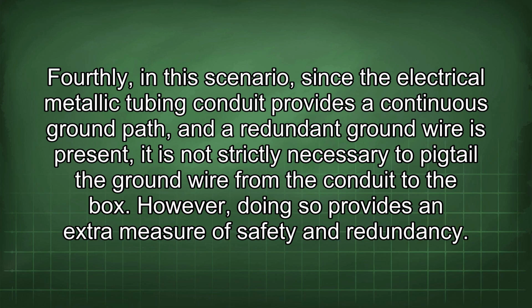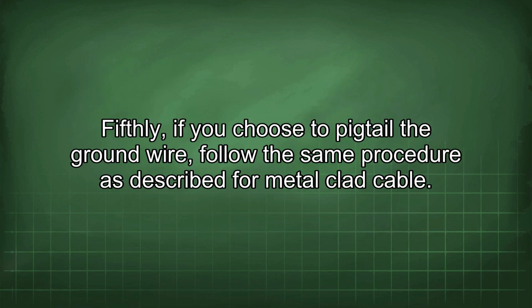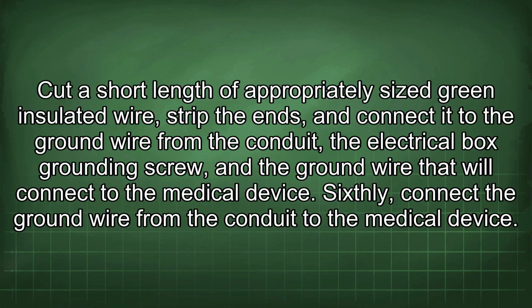However, doing so provides an extra measure of safety and redundancy. Fifthly, if you choose to pigtail the ground wire, follow the same procedure as described for metal-clad cable. Cut a short length of appropriately sized green insulated wire, strip the ends, and connect it to the ground wire from the conduit, the electrical box grounding screw, and the ground wire that will connect to the medical device.